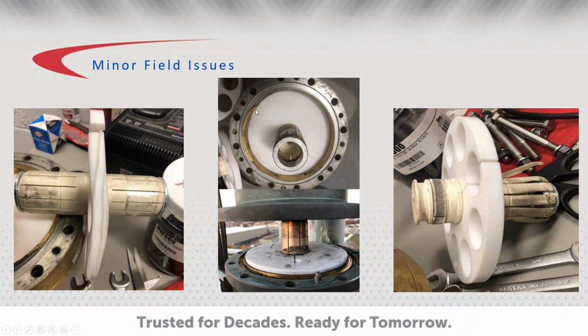Okay, so up here in this top part of the picture, you can see that the contact edge has been folded over, and that would become catastrophic if that was under full power and if it went unnoticed, because you're going to get a lot of series arcing between the two joints, and then over time that would just expand and turn into multiple sections of transmission line, or even worse, more lines becoming burnt up or affected from this.